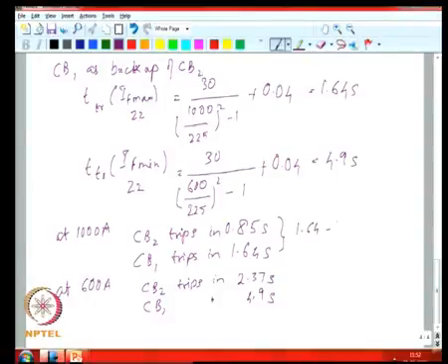In this case you have a margin of 1.64 minus 0.84, about 0.79 seconds, and here you have a margin of 4.9 minus 2.37, about 2.6 seconds. So the margin is greater than the 20 to 30% tolerances that might occur.